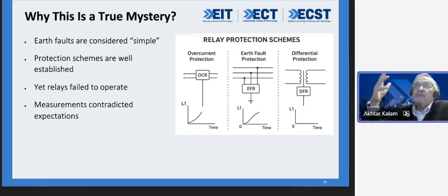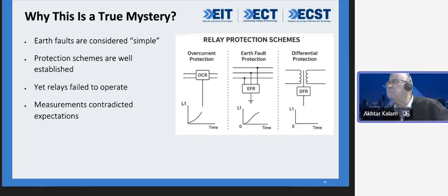Like, to give you examples, we have overcurrent protection. Since the time of Adam, we have had overcurrent protection. Nothing new about it, my friend. Adam and Eve knew about earth fault protection and overcurrent protection, differential protection. It's been there for donkey years. Then, as I said, if you ask any engineer, every engineer would say that we are very confident when there is an earth fault. We know that we can solve this issue.